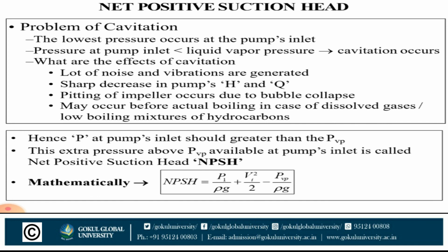Net positive suction head. Problem of cavitation. The lowest pressure occurs at the pump inlet. If the pressure at the pump inlet falls to the liquid vapor pressure, cavitation occurs. What are the effects of cavitation? A lot of noise and vibration are generated. Sharp decrease in pump head and discharge. Pitting of the impeller occurs due to the bubbles. It may occur before actual boiling in the case of dissolved gases and low-boiling mixtures of hydrocarbons. Hence the pressure at the pump inlet should be greater than the vapor pressure.